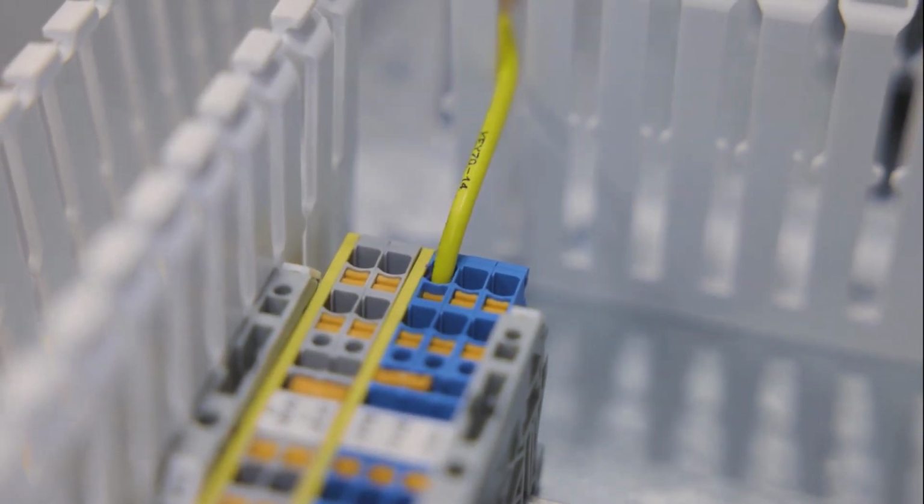And then you go all the way down to like the push-in terminal. You pair those with ferrules, and now a plant doesn't have as much maintenance later on. They don't have things that are loosening up over time as you have those interactions with vibration and thermal expansion or whatever. I mean, all that stuff is the unseen benefits that someone is getting out of all this.